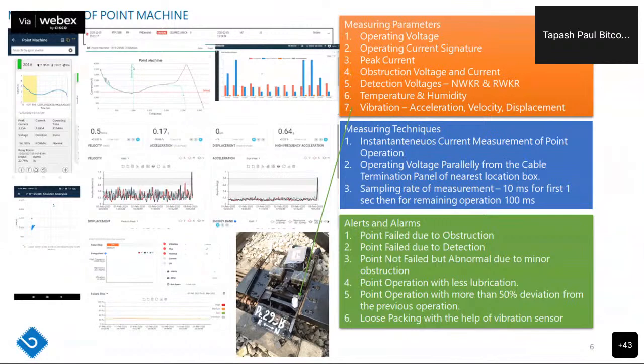We can see here in this chart the point operation — operating current versus operation time. For a good point machine, the good range is around 2 to 3, or 3 to 4 seconds, for the point operation to complete. If the operation time is more, taking longer, and the operating current is simultaneously increasing, this can indicate a soft obstruction or dryness in the point machine during set and lock. So this type of signature or data can help predict point behavior and identify, before failure, the classification of the point machine.